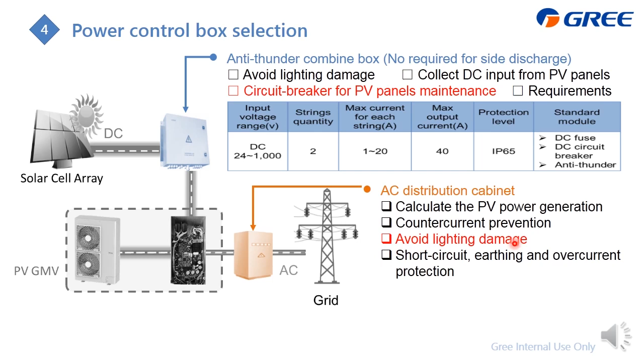Here is the detail of how to do the wiring from the PV panels to the outdoor unit. First thing first is to check the connection, which is the positive and negative. Here the plus and minus should follow this sequence. And then check the isolation with the megameter to ensure the isolation. And next is just to ensure this cable is well protected.